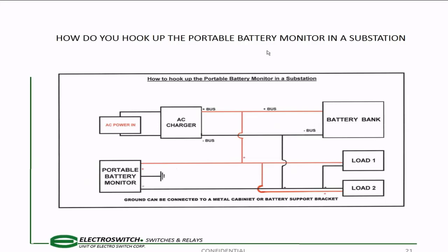This is how you hook up the portable battery monitor in a substation. So this is really simple. There's a common right here. You hook it up to ground, because if you actually have a ground in the DC bus, now I have a path to send out that pulser across to help find the ground. Other than that, this is my positive side hooking up between the AC charger and the battery bank, and my negative side hooking up to the negative bus between the AC charger and the battery bank. That's as simple as it gets.